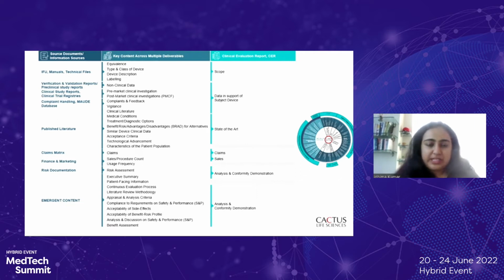As we all know, as per the MDR, it's not just a summarization of data. So the CER requires us to do a thoughtful analysis of all of the data. So once we've put together all of the data that we just discussed above, we look at the benefits of the device. We look at the risks of the device. Is the benefit-risk ratio acceptable? Are there any side effects? Are those side effects acceptable?